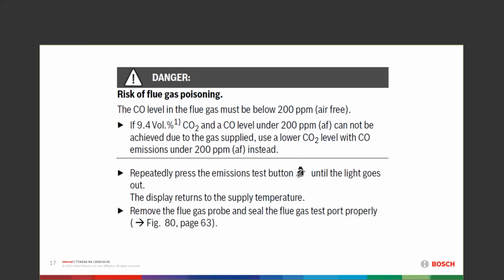Absolutely below 200 parts per million. With good setup, this boiler will do about 5 to 10 parts per million in low fire and somewhere between 10 and 50 parts per million in high fire on a Greenstar boiler. So real low readings. We see them as low as 0 or 1 part per million in low fire and down around the 10 in high fire.